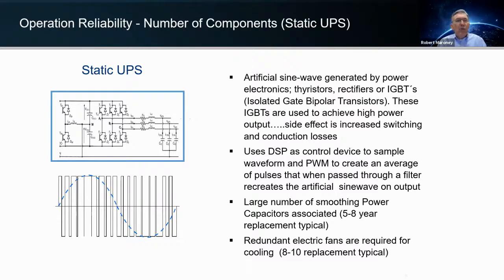When you're using a lot of power electronics like this, especially as you get above 500 kilowatts, you start to generate a tremendous amount of heat doing this conversion from AC to DC and back, and having to do multi-modules to get the capacity. Now what comes into play then is a lot of cooling fans. Between the capacitors and the cooling fans, we consider those to be single point failures and have impacts on reliability for the system.